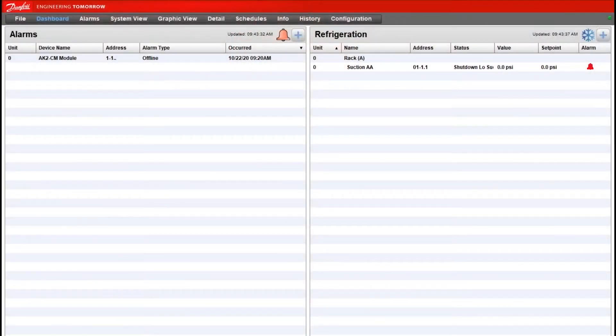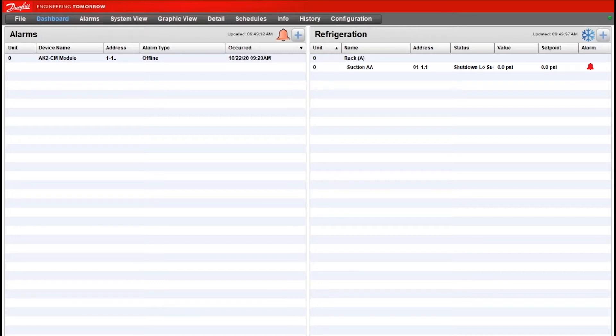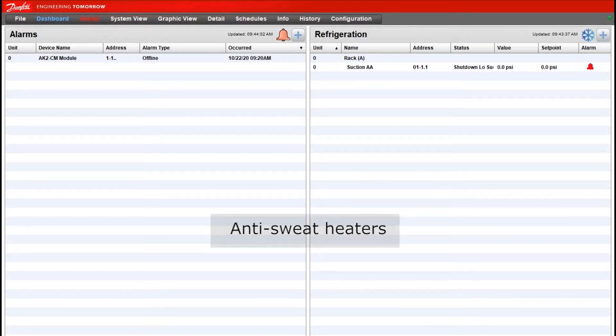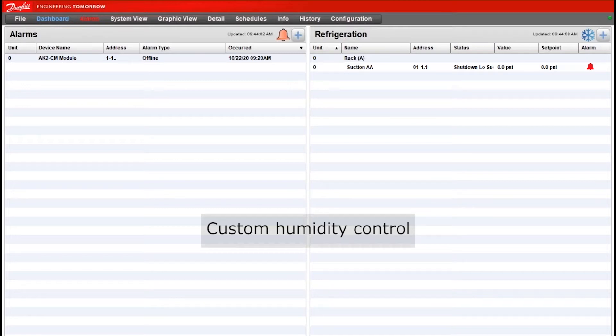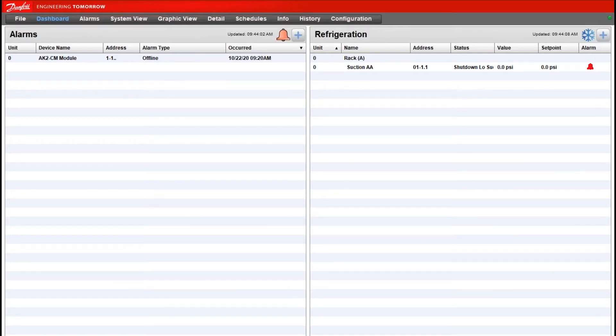In the System Manager, we may be looking to calculate dew point for a few different reasons. Anything with anti-sweat heaters on reach-in doors, or on the HVAC side in a rooftop unit with humidity control. If there's not something our controller can already handle with the predefined tasks, then we'll have to look at building the logic through a calculation to control.